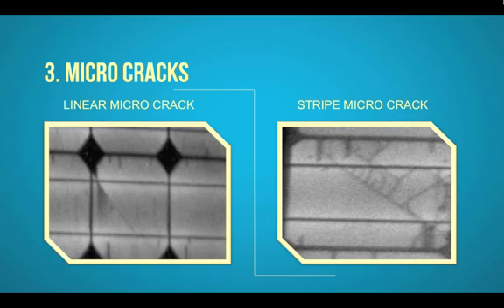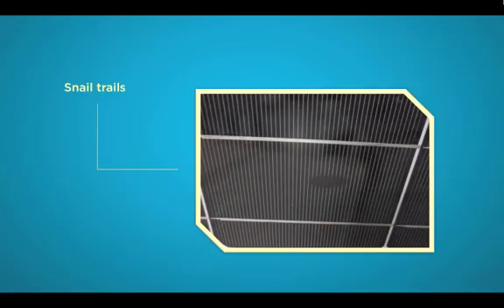Micro-cracks can be found through EL testing which is an imaging measurement process allowing to peer directly into the cells of a PV module and locate potential inherent defects. Visually micro-cracks may appear in the form of the so-called snail trails on the cell structure. However, snail trails can also be the result of a chemical process causing the surface of the cell to change or hotspots.